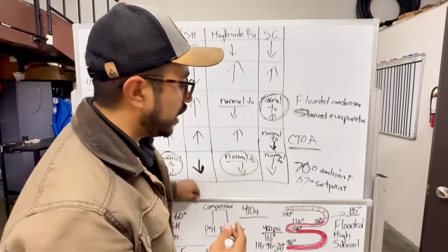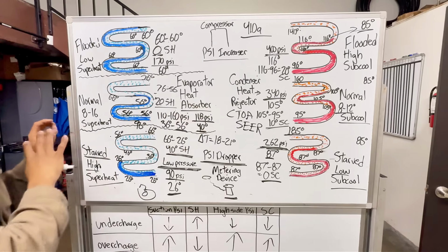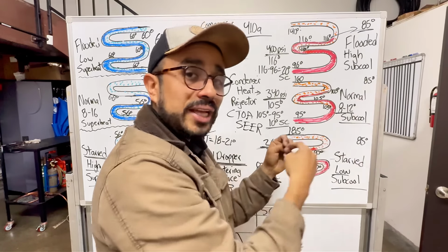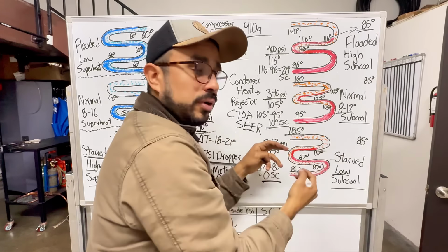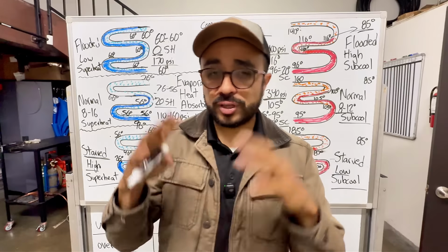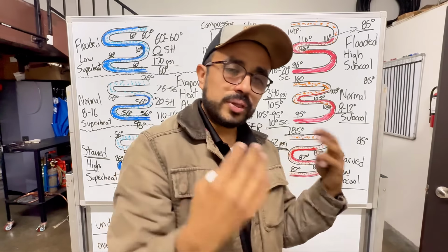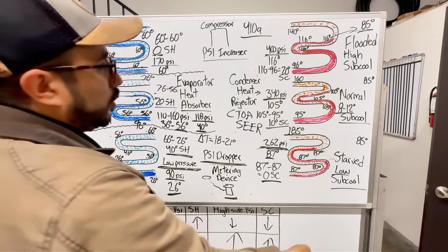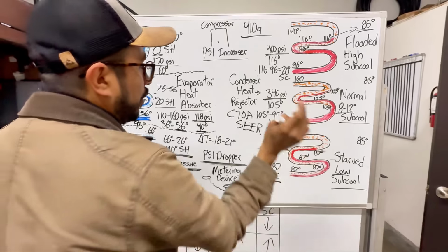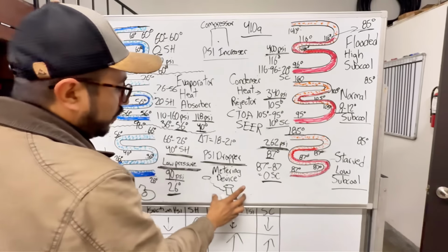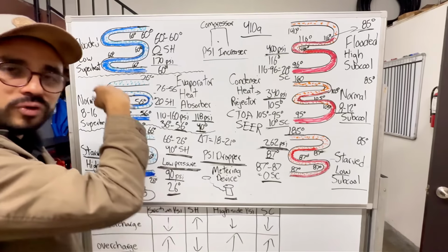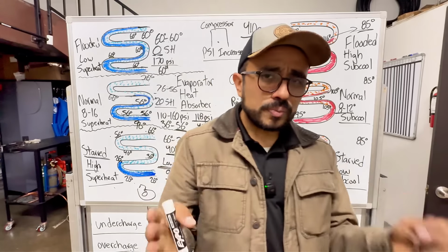But it is important to understand how superheat and subcool work. Condensing temperature must be greater than your outside air temperature, but not too much or not the same number, right? An okay number. Your return air temperature must be greater than your evaporator temperature. So that's the principle here, a temperature difference. But the refrigeration cycle is amazing. It works if it's properly charged and there's enough airflow. With the pressure increaser, which is my compressor, my heat rejector, which is my condenser, my metering device, which is my pressure dropper, and my evaporator, which is my heat absorber, it is doing the same thing over and over and over again.